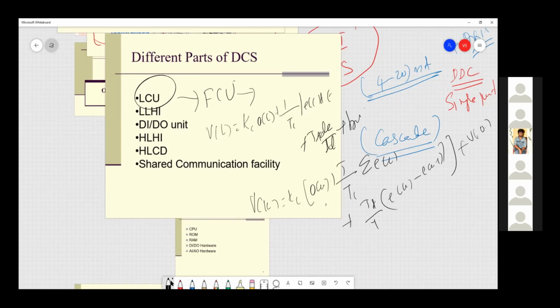If you want to do it in a discrete mode of operation, everything can be done in your local control unit. That's what is called the heart of your distributed control system. It can control the entire plant, maybe temperature control, pressure control, flow control, or a combination of flow and level, using any type of control system, simple feedback, feed forward, cascade, or ratio. So everything you can design in your control algorithm by means of your LCU. That's very important, it's the heart of the distributed control system.